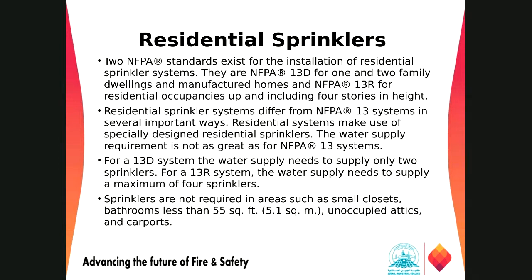There are two NFPA standards which exist for the installation of residential sprinklers, right? Which is NFPA 13D for 1 and 2 family dwelling units, and we have NFPA 13R for residential occupancies, right? So residential sprinkler systems are totally different from NFPA 13 in several respects. For example, in the residential buildings, we need a sprinkler system which is totally designed for residential purpose, right? And those should be installed only in those occupancies. And we don't need as much water supply for the greater demand as for NFPA 13, right?